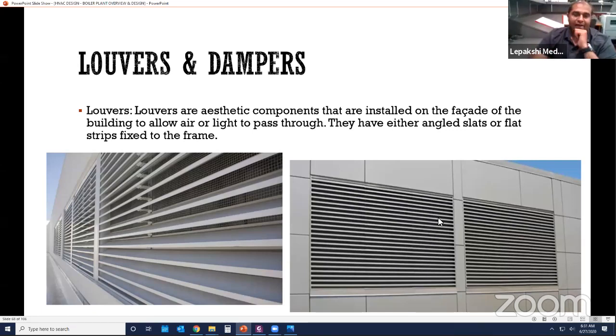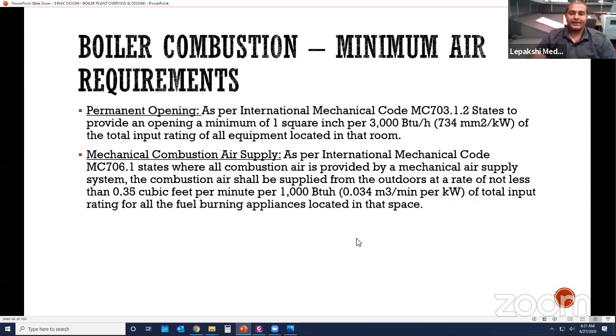Now, you need air for combustion. How big are these things sized to be? You could make the openings big, like 20 by 20, who knows? But you don't want an opening of size 20 by 20, so there are some restrictions. The codes say how much air is required. As per the International Mechanical Code, section 703 states that you have to provide a minimum of 1 square inch of opening for every 3000 BTU/h input of the boiler system.